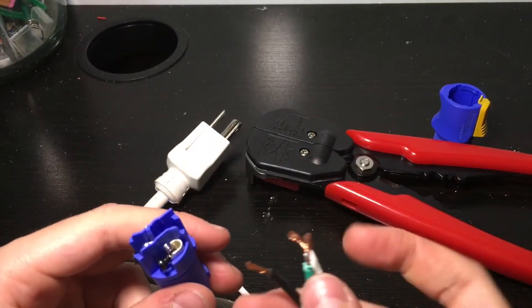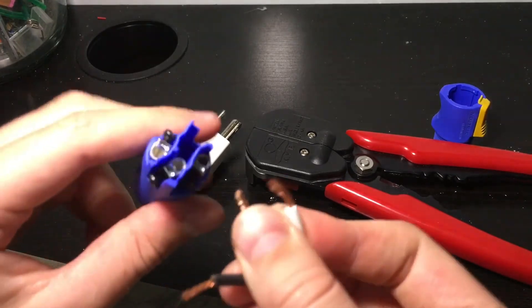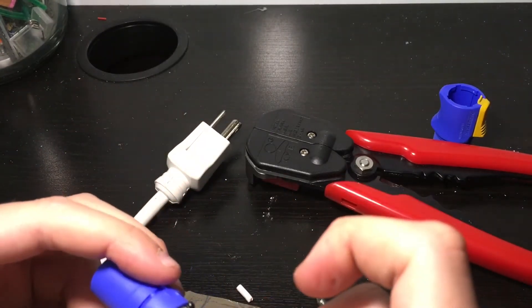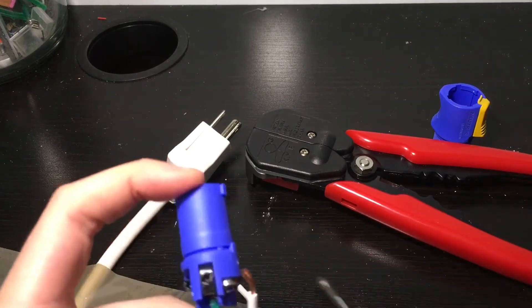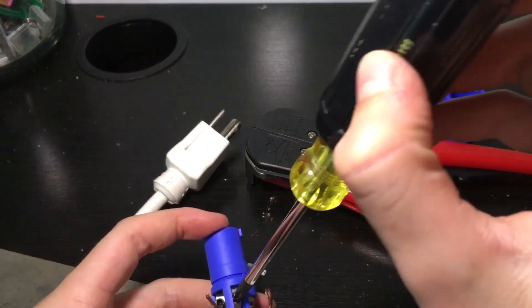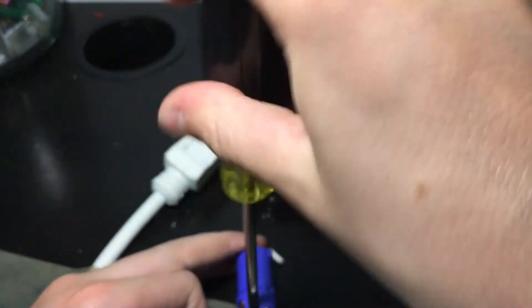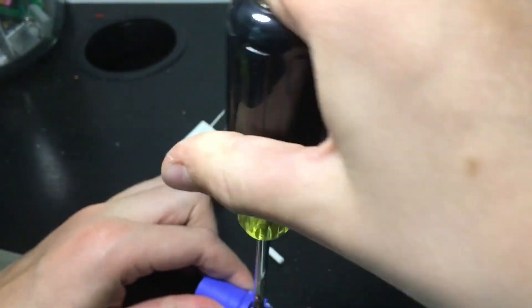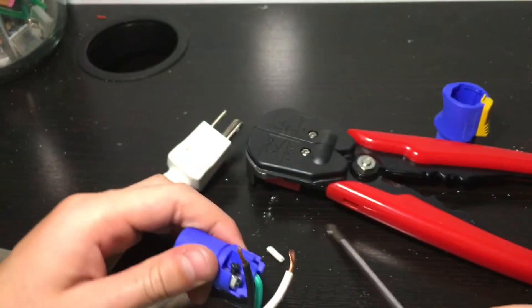You're going to take the green and put it into Earth. Make sure it's tightened down all the way, because you don't want these pulling out in your cable because it's very hard to fix it if they pull out. So tighten it down as tight as you can without stripping it, of course.